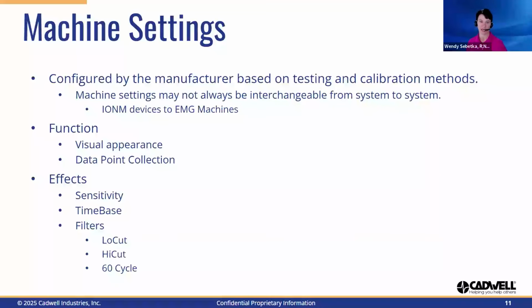Changing these from the default settings should be done with caution and only when necessary for a specific purpose, such as research. The best method of handling 60 Hz interference is to locate the source and eliminate it. But when that is not an option, the 60 Hz or notch filter can be very beneficial in reducing 60 Hz noise for sensory studies and as a last resort for EMG. The 60 Hz filter should never be used for motor type studies, as this will filter out necessary parts of the waveform and alter your responses.